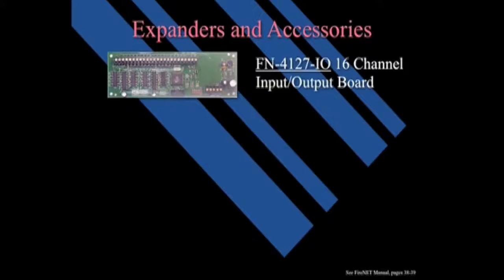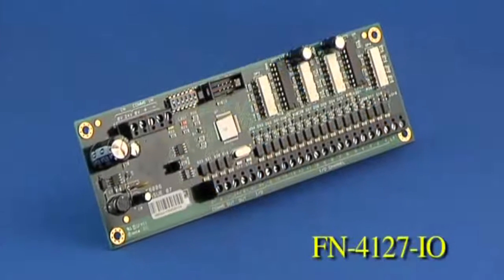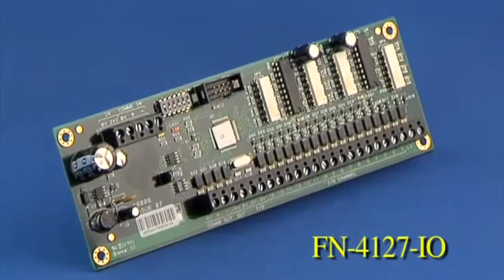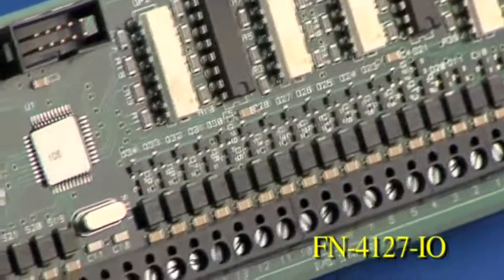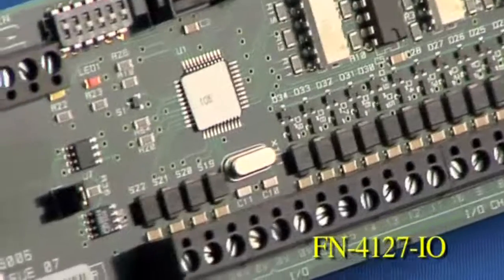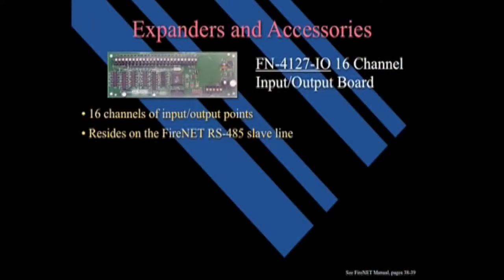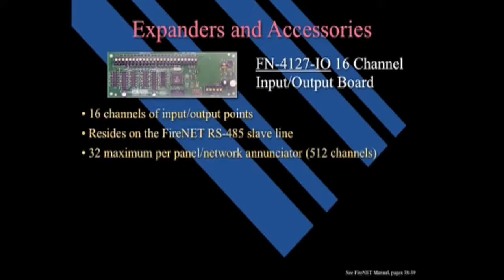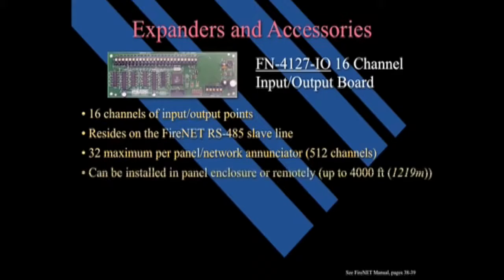The FN4127-IO is a 16-channel input-output board. Each channel can be configured independently as an input or output point. It resides on the RS-485 slave line. The RS-485 slave line on the FireNet panel can support up to 32 4127-IO expansion boards. The I/O board can be installed in the panel or remotely up to 4,000 feet.